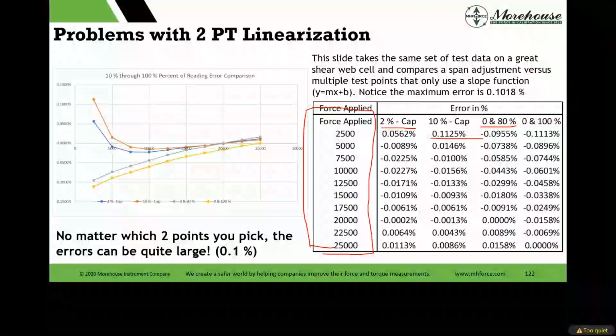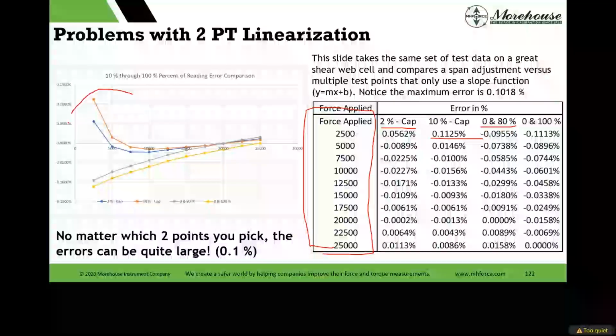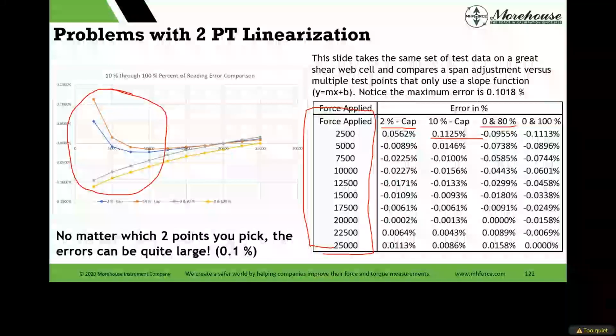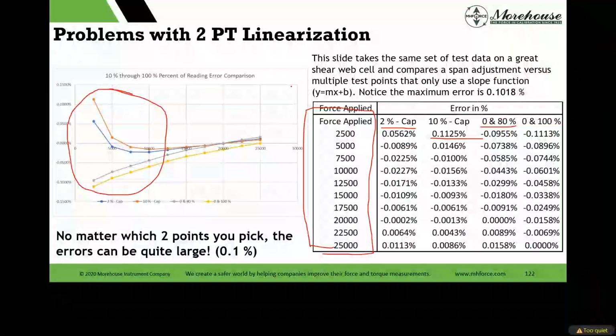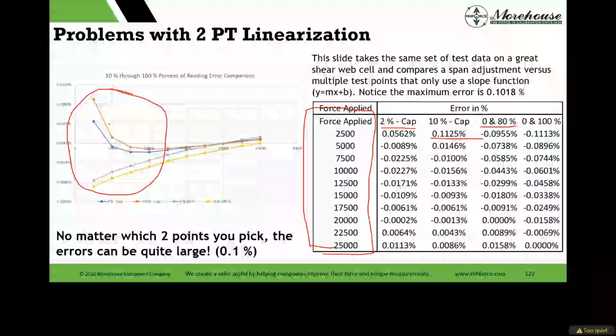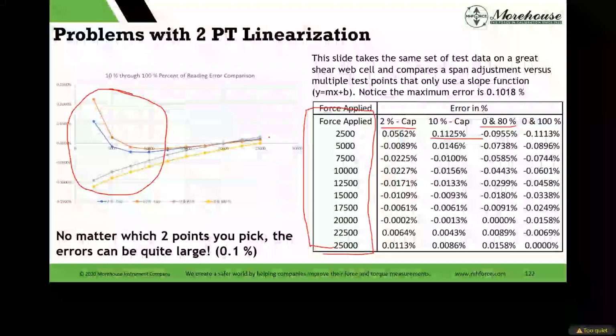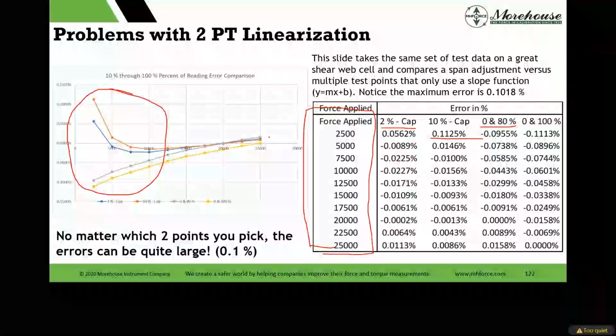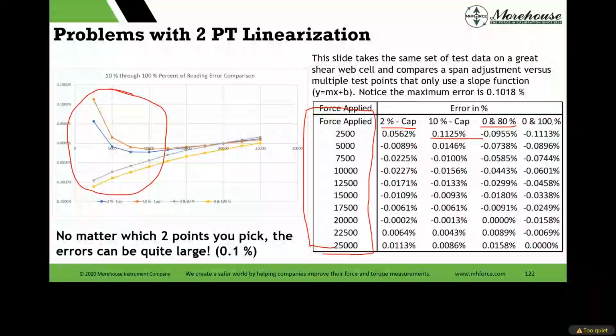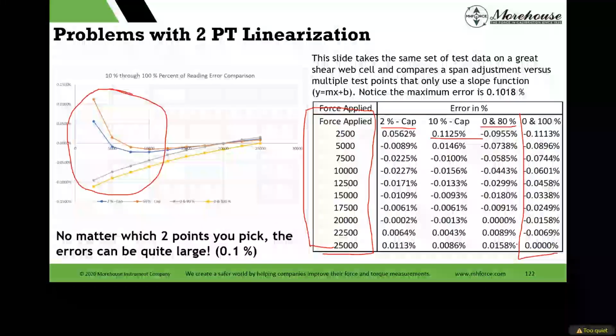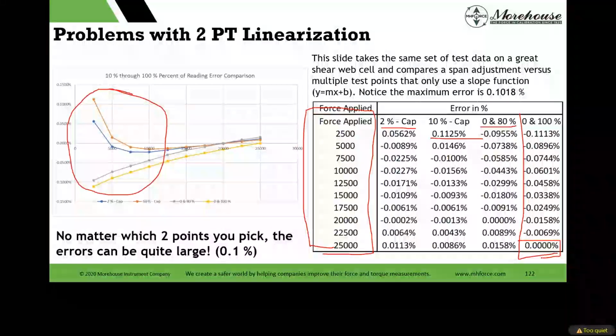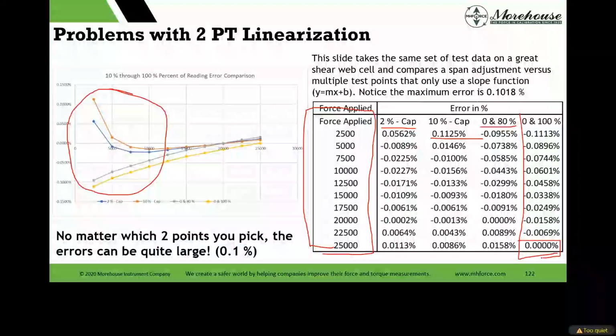Though something's going on here, we have quite large errors at the bottom end no matter what we span in. One went positive at 2,500, and the other went negative, and you can see how these errors went. Then they all typically come together at capacity. When I span at 0 and 100%, my capacity number, so at 25,000, when this reads 0 over here, that means my indicator reads 25,000.